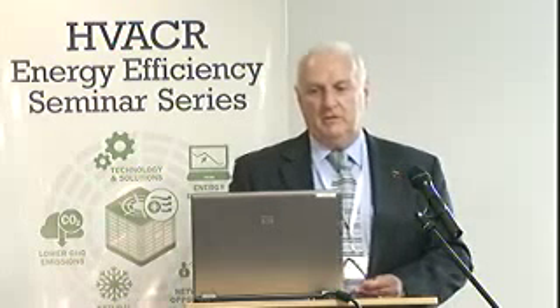So the first one on supply voltage, and this was touched on by Sam. There's an Australian standard that changed in the year 2000. Prior to 2000, the Australian supply standard for the guys where I worked was 240 volts plus or minus 6%. It changed in the year 2000 to 230 volts plus 10% minus 6%.